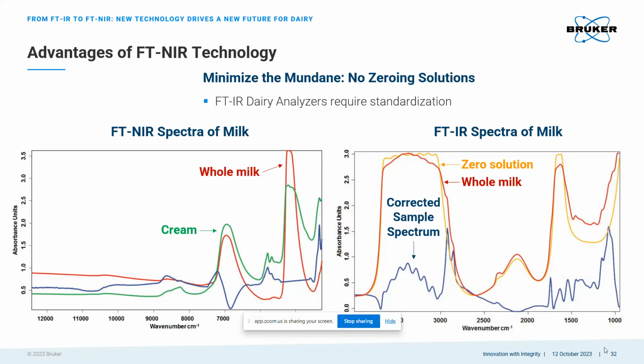Because for the evaluation of NIR spectra, no compensation for water is required, which we can see on the left graph. And for NIR analysis, the flow cell is actually retracted and a background measurement is performed with an open beam or air and not through a flow cell that's filled with water. So we're eliminating potential sources of error as well as mundane tasks for lab personnel.